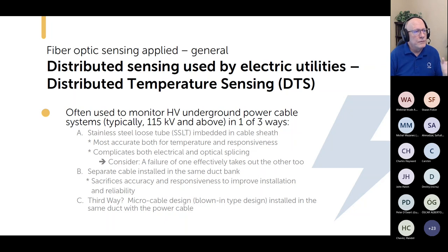And I don't like systems where the failure of one aspect of the system takes out the rest of the system. So that's, to me, a significant disadvantage of this concept of embedding a stainless steel loose tube in the cable system, because if the optics fail, then I've lost that capability. So now I can't monitor the condition of my power cable anymore. And the only way to fix that is to replace the entire cable, and those tend to be expensive cables. But likewise, if the power cable fails, like there's tracking in the insulation that leads to a failure, that's going to blow your communication system as well. So again, the only solution is to replace everything. So I'm not really a big fan of this approach, but it is done.